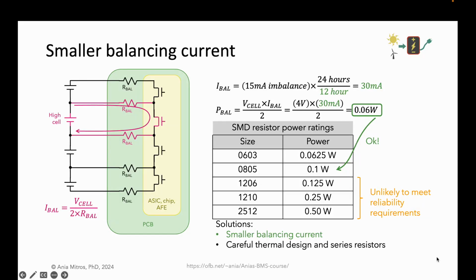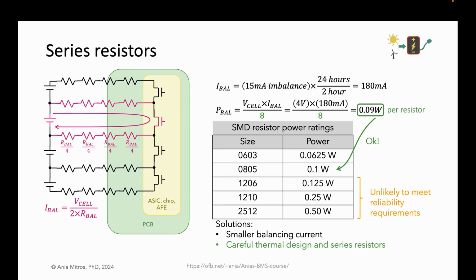A smaller balancing current can meet our constraints if we balance a larger fraction of the time. For example, if we decide that balancing 50% of each day is okay, then we can reduce the balancing current to 30 milliamps, requiring only 60 milliwatts of heat dissipation in each balancing resistor. An 0805 size surface mount resistor is rated to handle that.